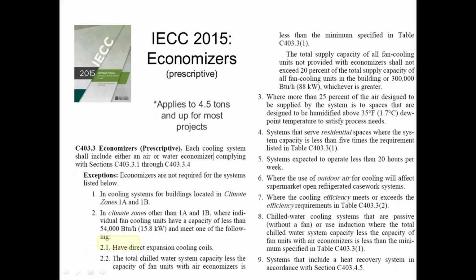When are economizers required? For most systems in Illinois, climate zone 5A for Illinois, 54,000 BTUs and up, I'm going to have an economizer, right? That's 4.5 tons essentially. This is actually less stringent than the 2012 code, where we had to do it for 33,000 BTUs and up. So this has been relaxed a little bit. It's one of the few things in the code that got less stringent than the previous version, probably because, as you might know, this section does not apply just to rooftop units.